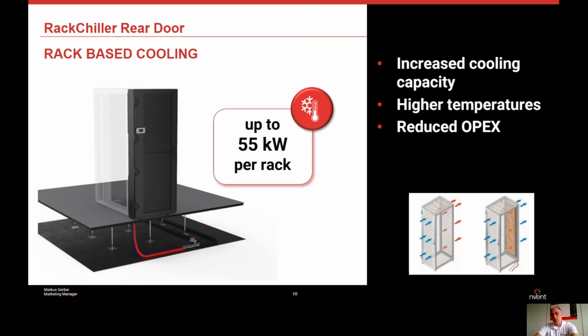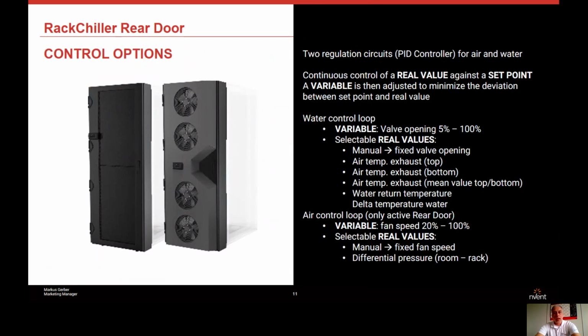And even with a rack-based cooling solution, if you have all your racks equipped with these doors, in case of any failure, the other ones take over. So the room is not really heating up, and the equipment is taking the air from the room. Let's go a little bit more into detail on the regulations.